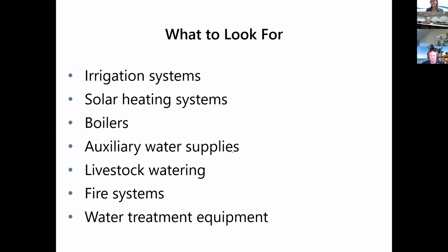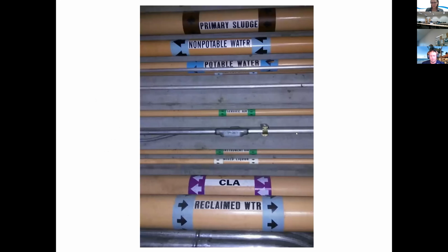All right. Well, we're going to get into the fun part now. So you're going to go out and you're going to do a hazard survey. You show up, and there are pipes running everywhere, and only one of them is potable water. One of the things you're going to look for is, does the labeling on this potable water line change further down the road? Which you'll be shocked that sometimes it does. It'll just magically turn into something else, or something else will magically turn into potable water. And it's like, hey, what happened there?